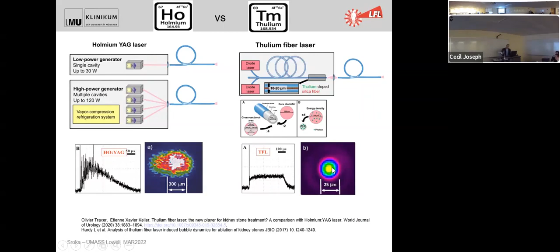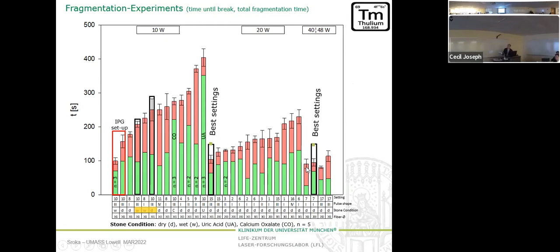We did experiments with these new laser systems on the fragmentation process and also on the propulsion process with different parameters, and that is what we learned there. Yes, we have these curves. Here is the break time, and then we have the chasing time and destruction time. And we found some best settings in the 20 watt regime, but also much better in the 40 watt regime. We also found that the destruction is very high, especially the dusting. Related to the different parameters we used, we have between 70 to 90% dust, so just roughly 30 to 10% fragments.